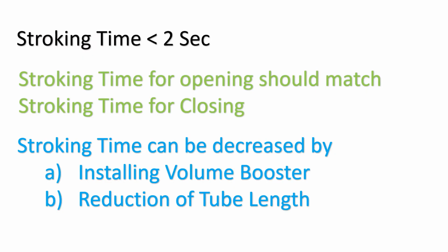So first we will be discussing the stroking time of the control valve. So the normal thumb rule is to keep the stroking time less than 2 seconds. This means that when we give a step input, the valve should open within 2 seconds.